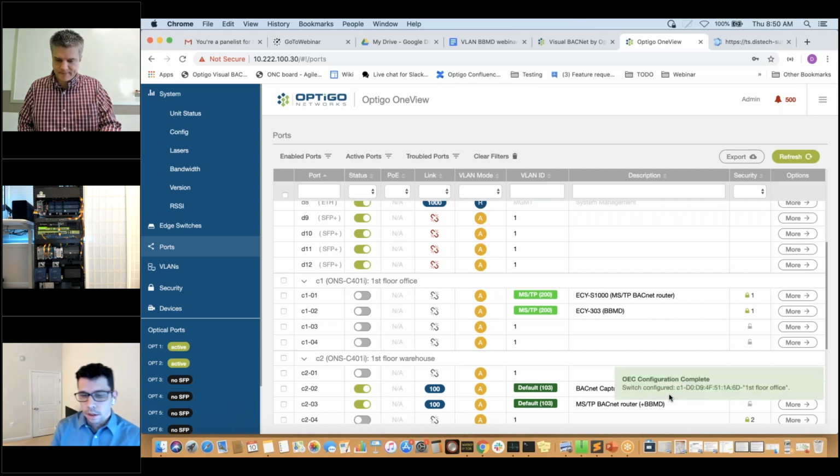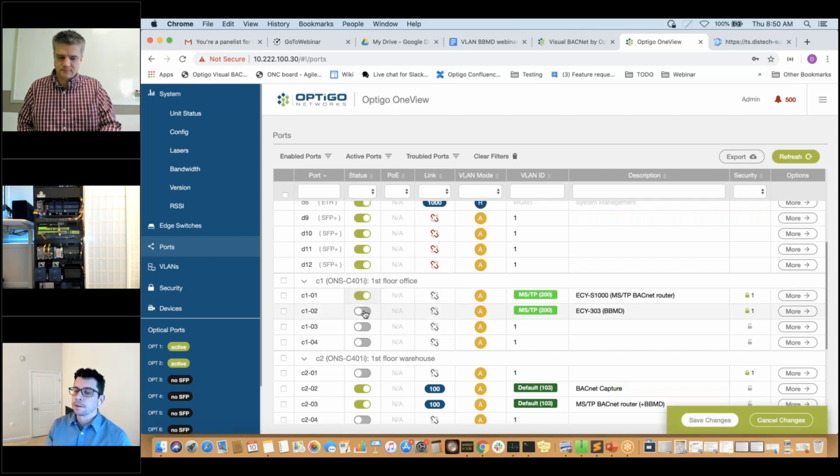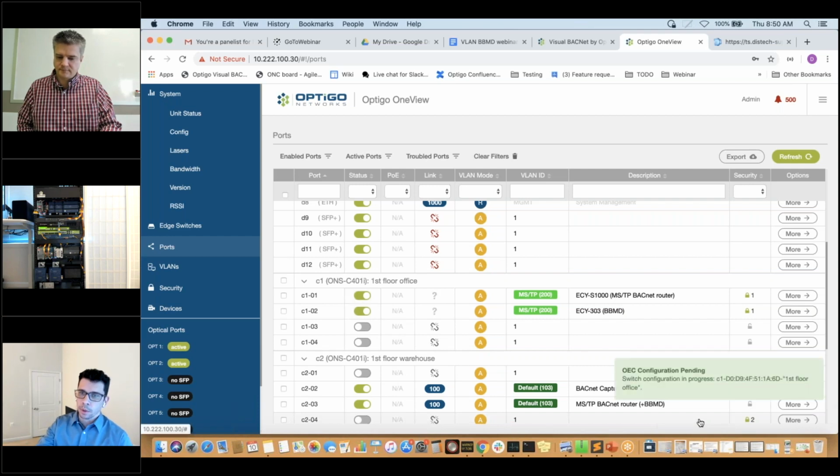So what Dave's doing here is, anytime you switch VLANs, it's good to go ahead and cycle the port, because when the controller sees that there's no network connection, the connection will go down. And one of the things most controllers, not all, but most, will typically do when a connection first comes up is ask for a new address just to verify. Some controllers won't. If they have an extended DHCP lease, some types of controllers or IP devices out there may not ask again. So you may have to power cycle those controllers to get them to respond.